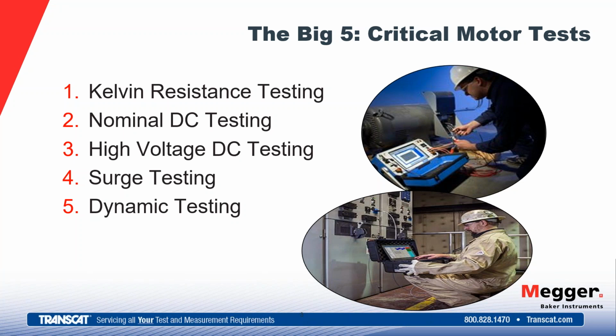The fifth test, which is actually not a test as such, but a monitoring of the motor while it's running. So dynamic monitoring of the motor. We're going to hook on to our currents and voltages of that motor while it's in its normal operation environment. And we're going to take a look at the voltages and currents and then do some math, and we get a lot more information there as to the environment that motor is living in. So these are the 5 tests that I would like to take a look at through this presentation.